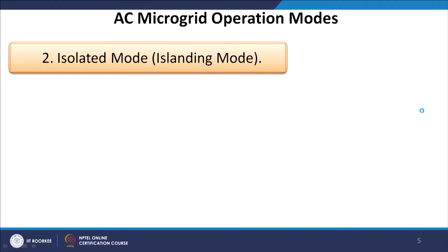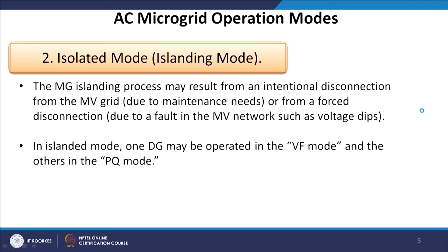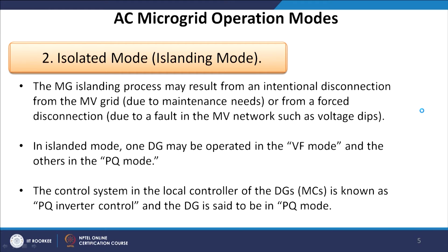In isolated mode of operation, the microgrid islanding process may result from an intentional disconnection from the medium voltage grid, or from a forced disconnection due to a fault or voltage dip. In islanded mode, one DG may be operated in VF mode and the others in PQ mode. The control system in the local controller of the distributed generation is known as PQ inverter control, similar to grid-connected operations.